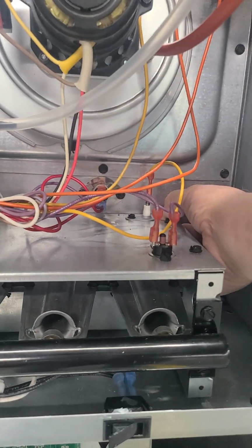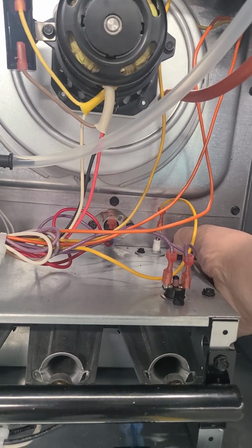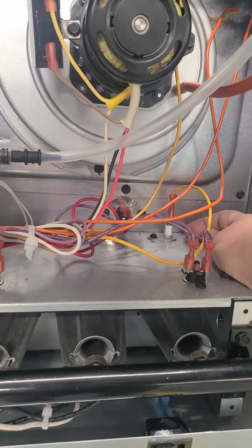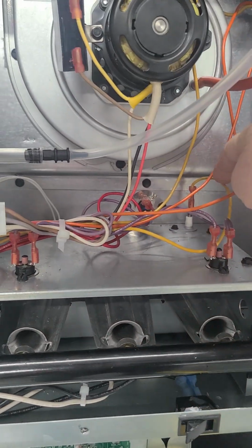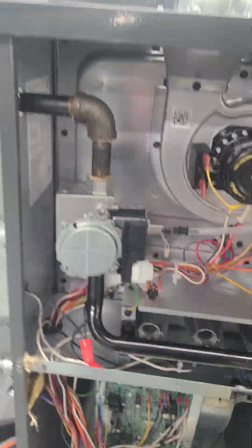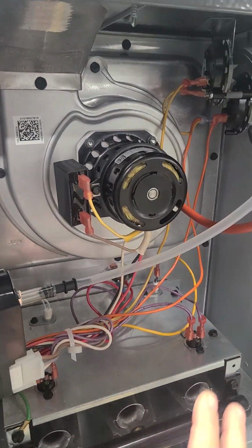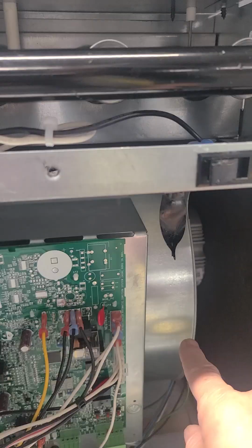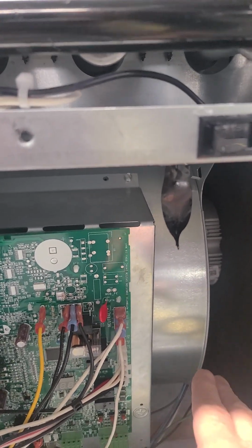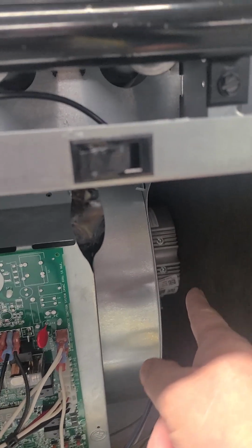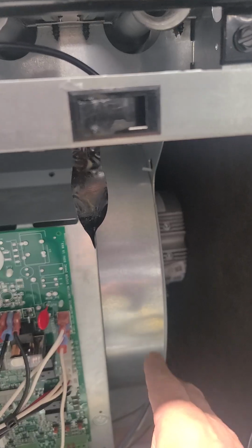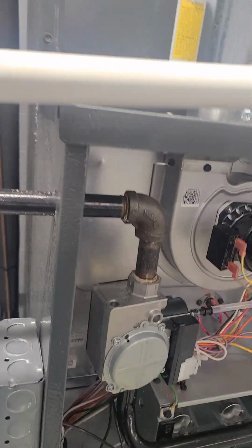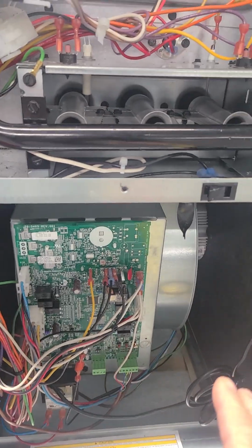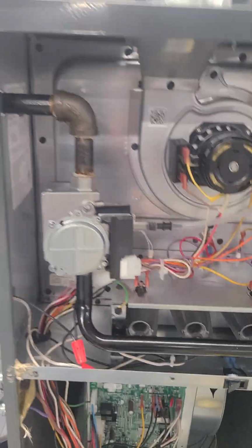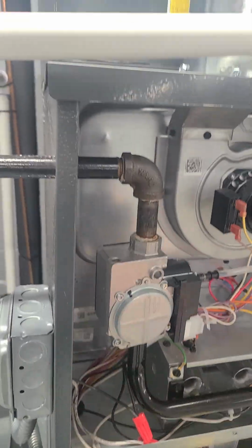And then back here, the flame sensor is another safety device, or sensing device, for the circuit. As long as that flame sensor is sensing that there is a flame in the burners, as long as it's still being called for heat, the gas will remain on. Now, once the burners are running and the inducer is running, there is a pre-programmed delay for the, in this case, ECM centrifugal blower motor, and then that blower motor will run the air across the heat exchanger and heat the conditioned space. Now, there are algorithms also pre-programmed that can vary the speed of this motor, along with the gas valve being two-stage, high and low gas being supplied.